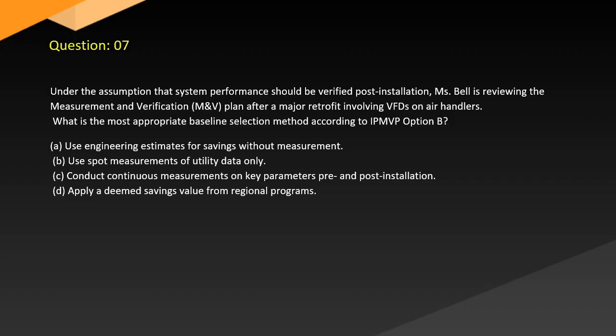Question 7. Under the assumption that system performance should be verified post-installation, a technician is reviewing the measurement and verification, or M&V, plan after a major retrofit involving VFDs on air handlers. What is the most appropriate baseline selection method according to Option B? A. Use engineering estimates for savings without measurement. B. Use spot measurements of utility data only. C. Conduct continuous measurements on key parameters pre and post-installation. D. Apply a deemed savings value from regional programs.